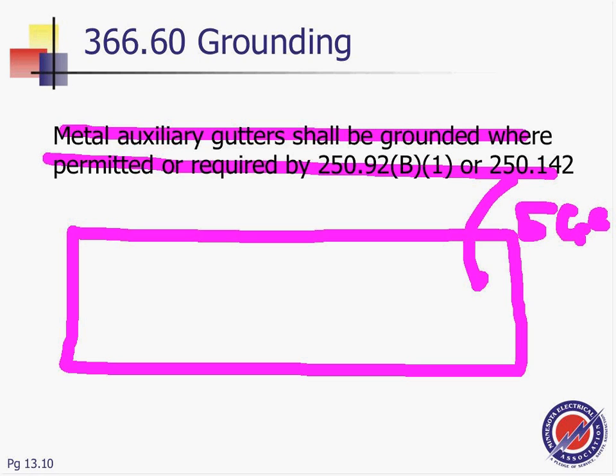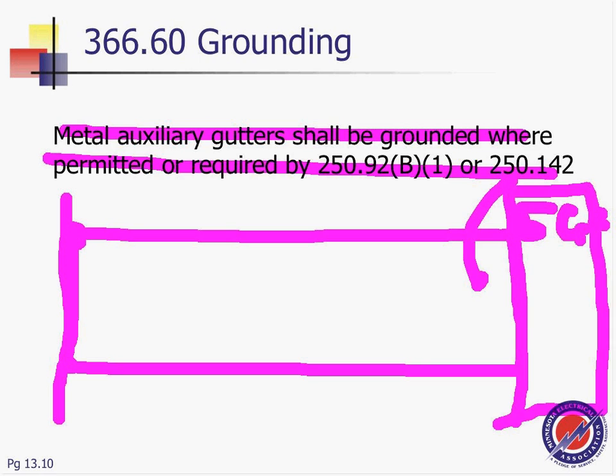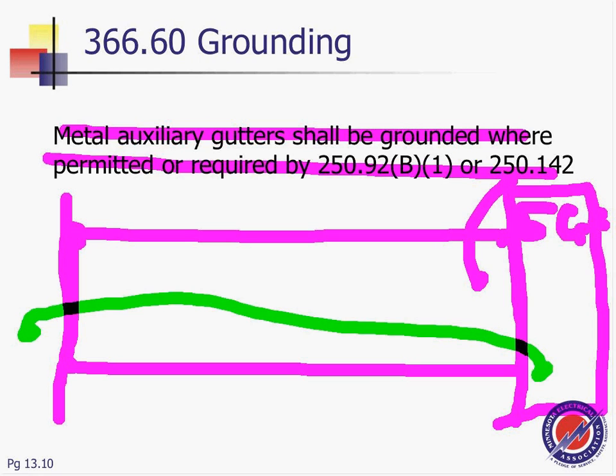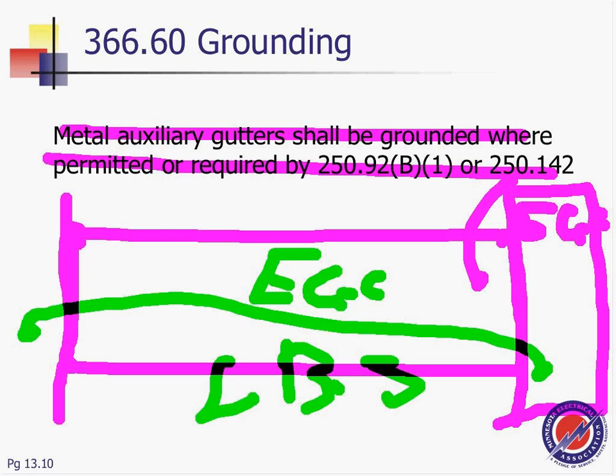So it has to be tied. Again, if it's between two panels, it acts as a grounding system itself, like any panel, so you have to add a third one. If you're tying between two panels and it's metallic, it has to act as an equipment grounding conductor. If it's non-metallic, then you have to bond the two equipments with an equipment grounding conductor or a bonding jumper between the two elements.